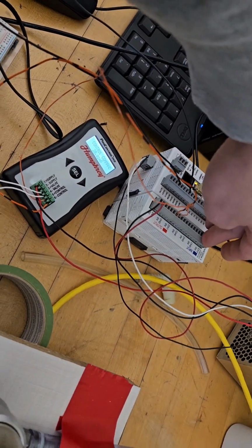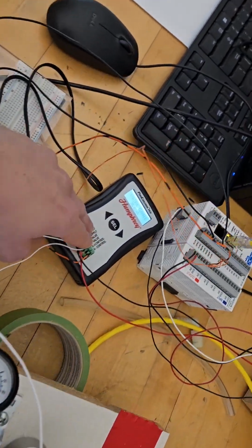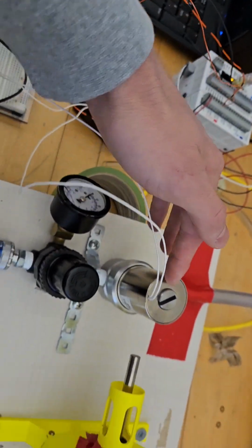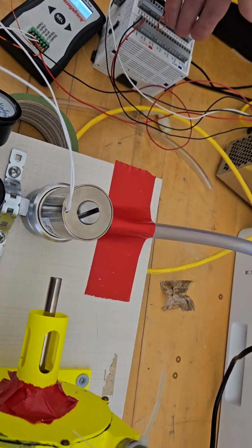For our turbine setup, we start with the power supply. It first sends power to the PLC and this node as well, because this doesn't have power, so we have to supply it with power. It runs the 24 volt and the 0 volt. We then have it running a current signal out of channel 1 to the PCD, which then supplies a current, as you can see on the screen right there, to the control valve to adjust the valve open or closed, which is supplied from the PLC itself.